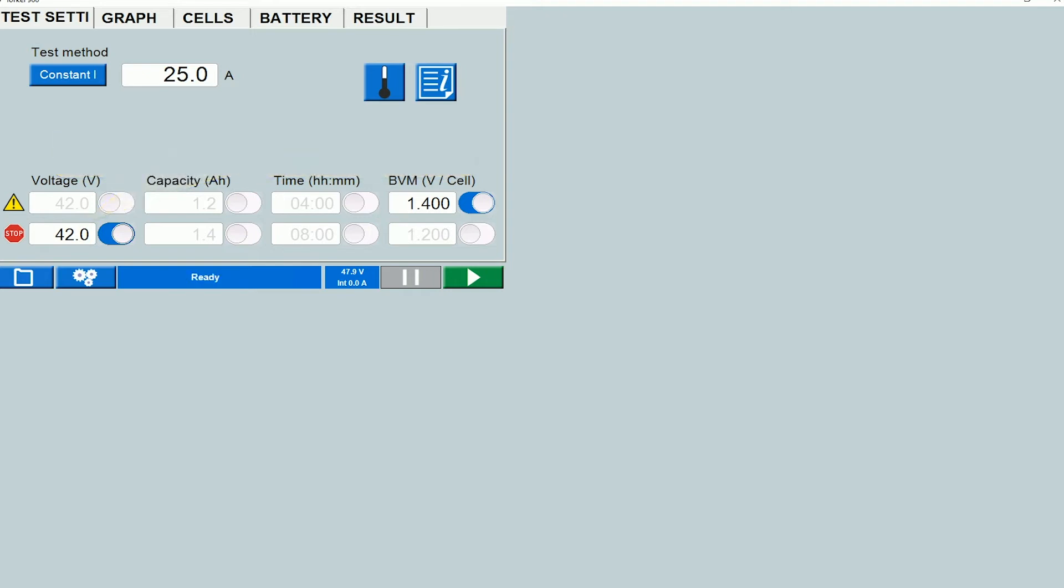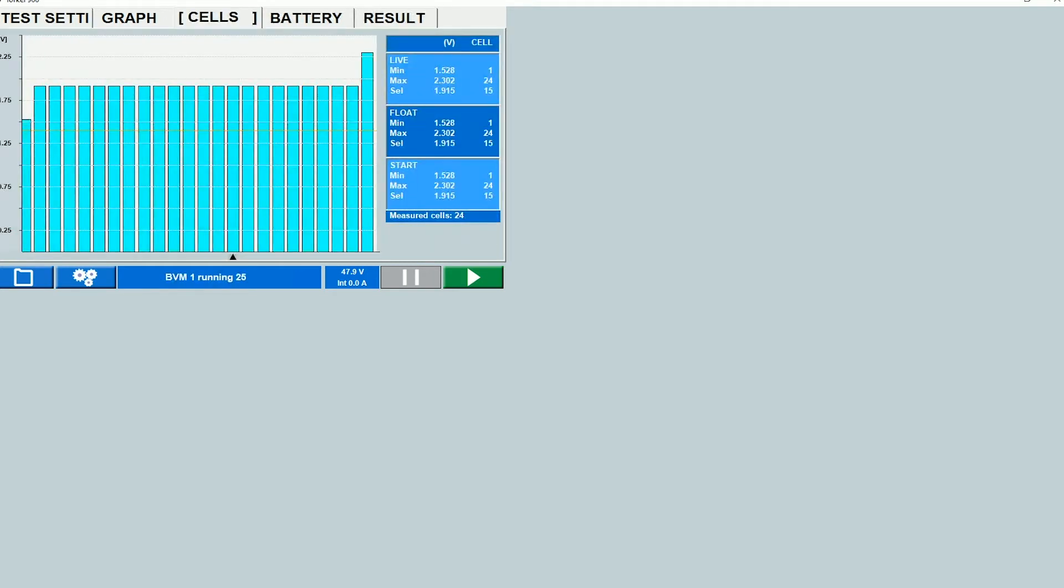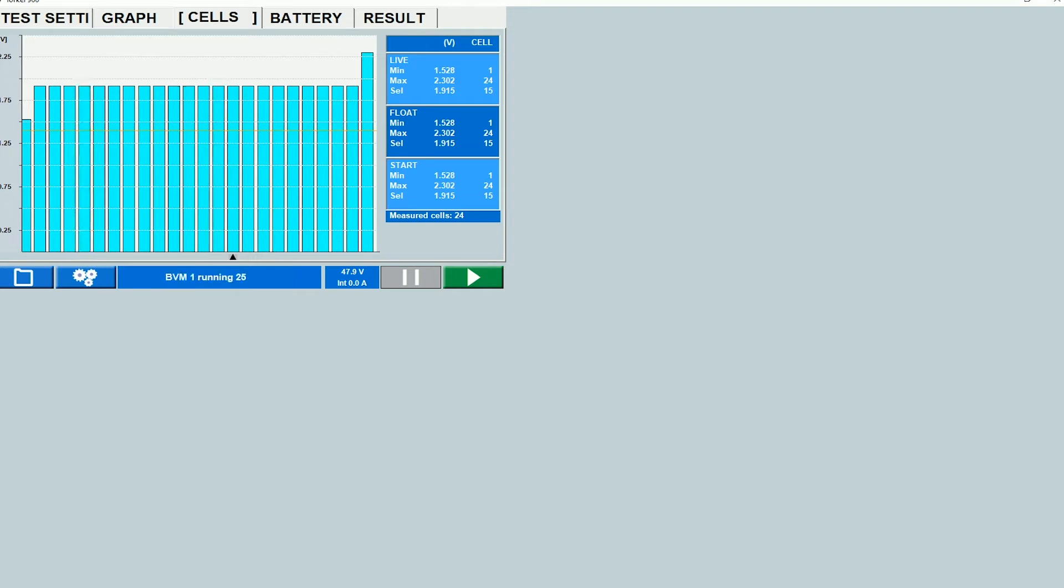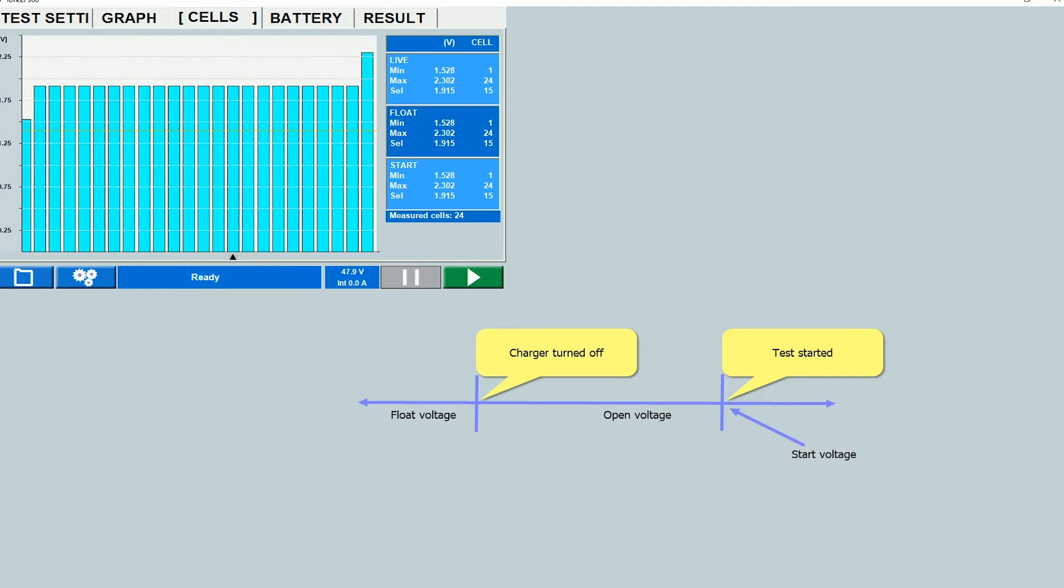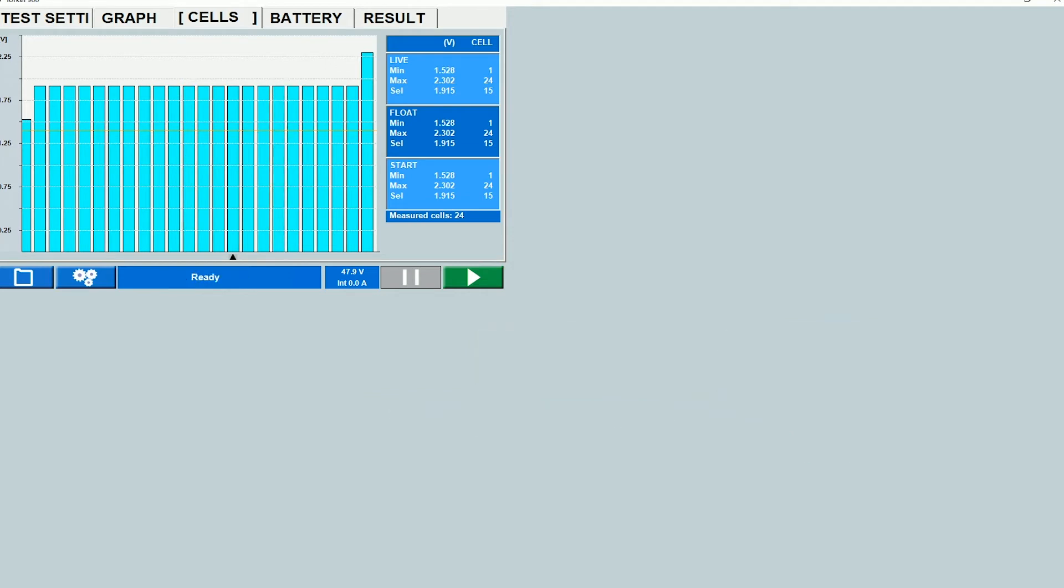So once you have done all the settings in this tab, you will switch back over to the cells tab and then at this point you will turn off your charger. So up until this point the charger is supposed to be turned on and the battery is supposed to be in the float condition. When we turn off the charger, what it does is the instrument was measuring the float voltage up until this point and as soon as you turn off the charger, the voltage changes by a little bit and the instrument senses that and it measures the open voltage.